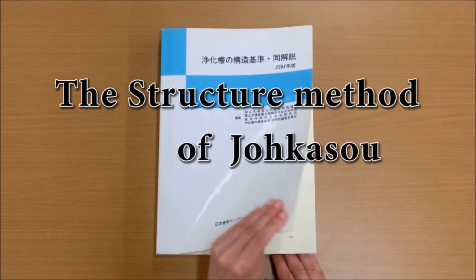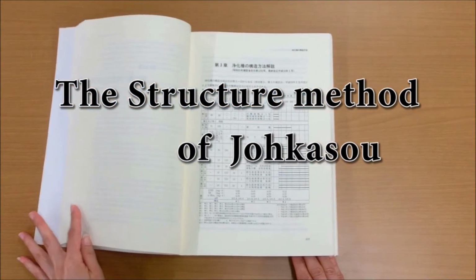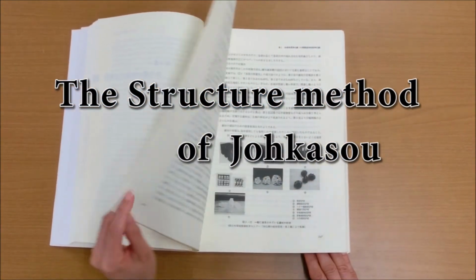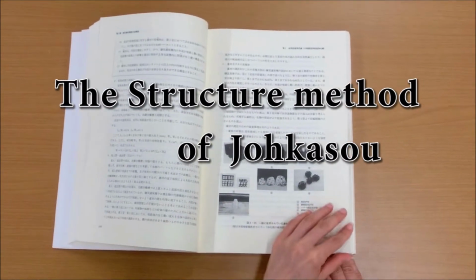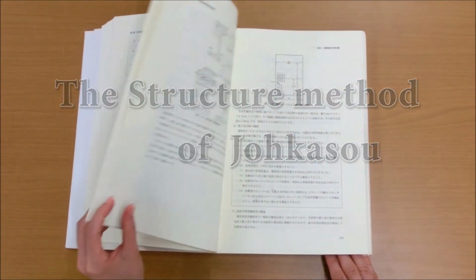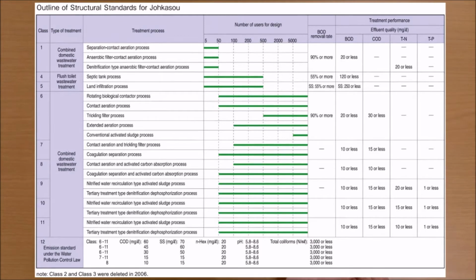The structural method of JOHKASOU has been notified in the building standards. This is also called structural standards for JOHKASOU. Standards require JOHKASOU to remove organic pollutants with effluent BOD concentrations of less than 20 mg per liter and to also remove nitrogen and/or phosphorus.